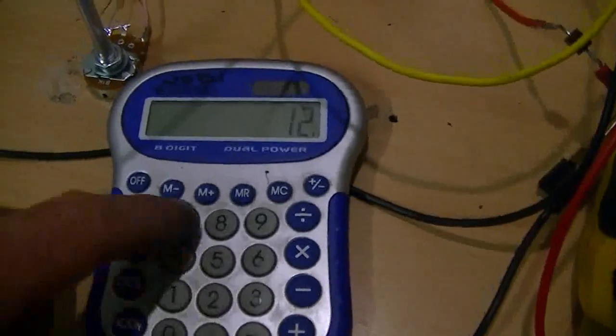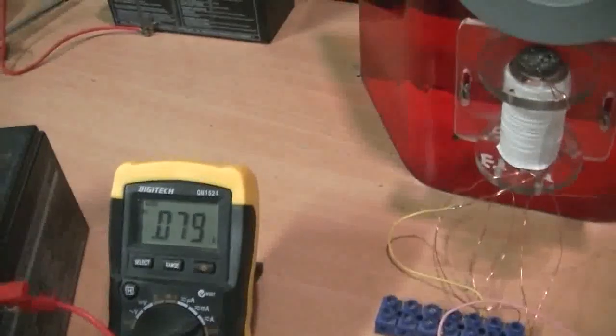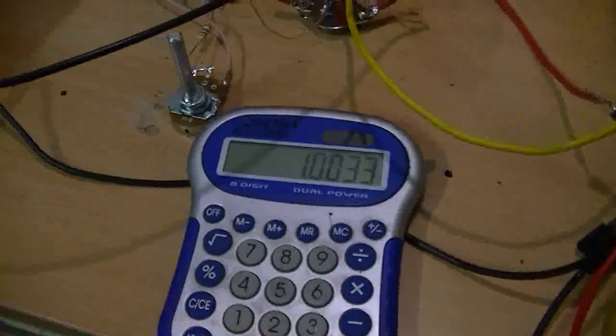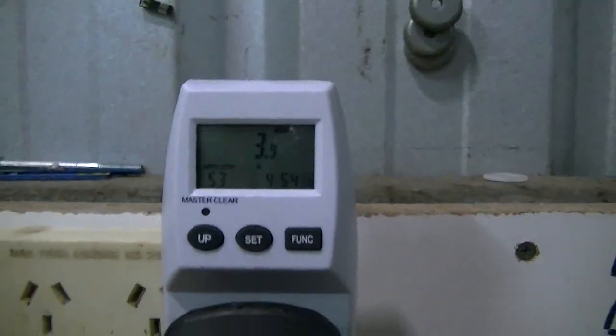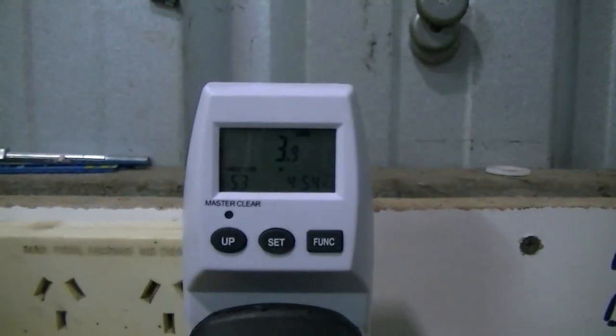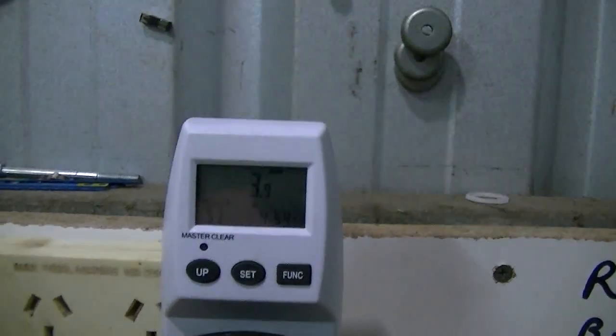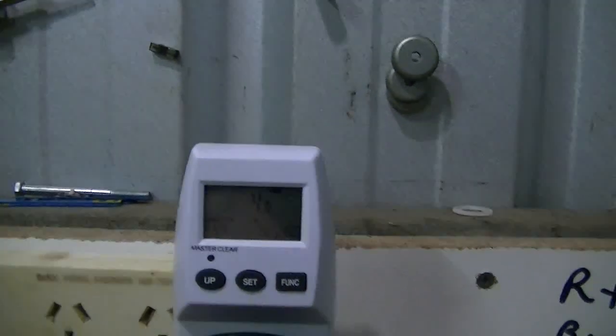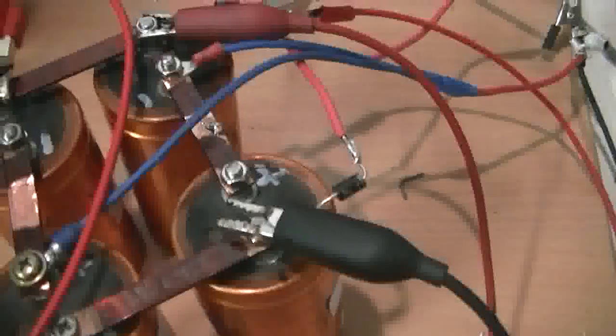So if I just go 12.7 times our milliamps, 0.079, that gives us 1 watt as well. So that 1 watt we could take off of that as well, because we're getting that back out of the system. So the 1 watt plus the 1.3 through losses in the transformer gives us 2.3. That would bring that watts down to what, 1.6 watts being fed into those caps.